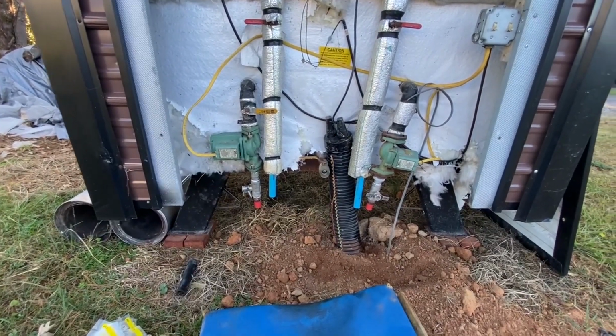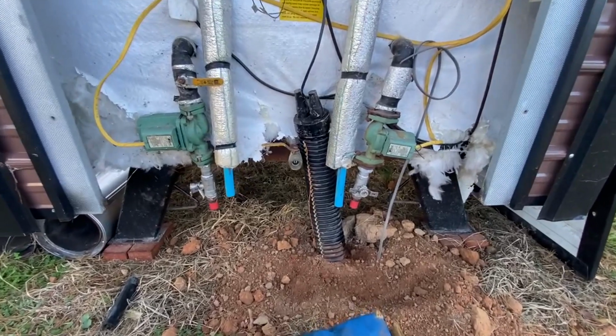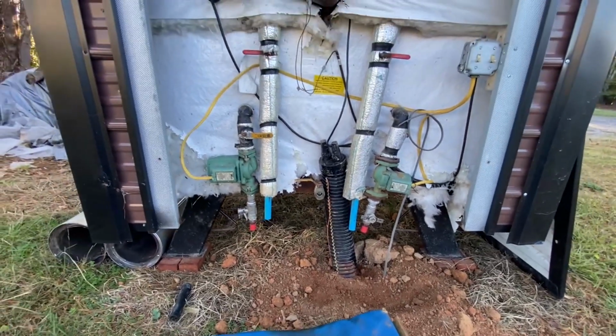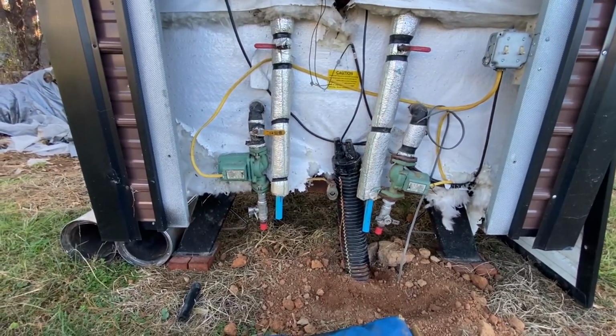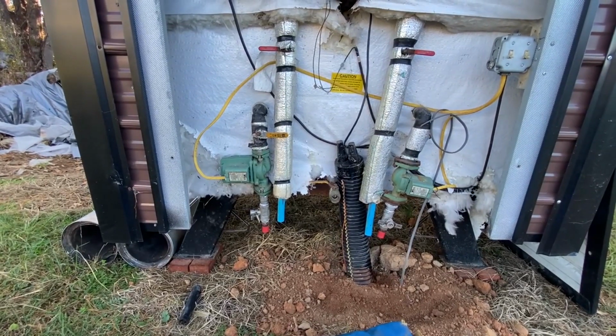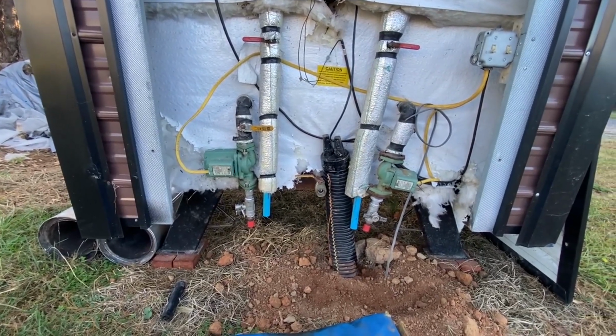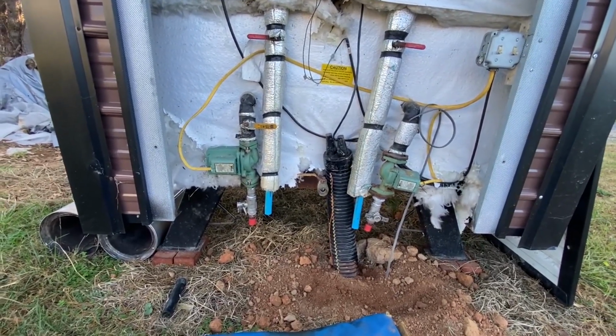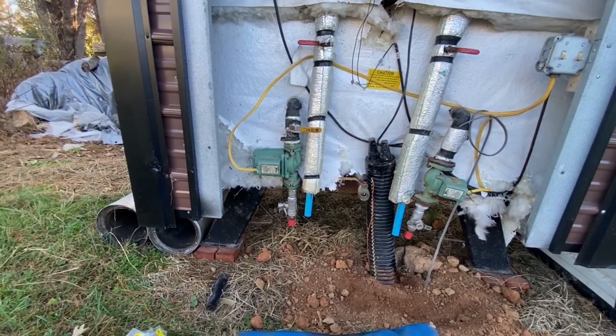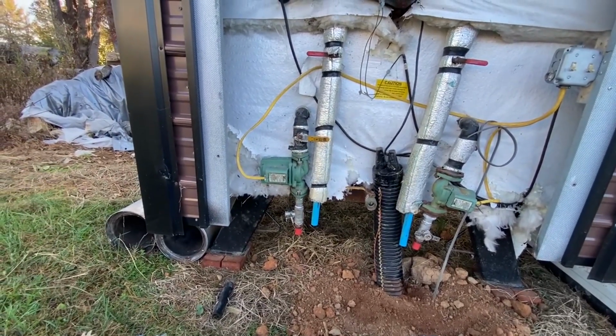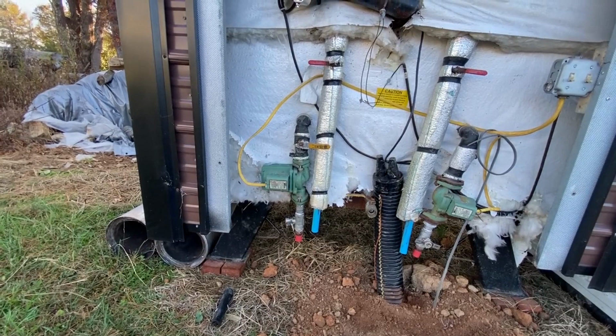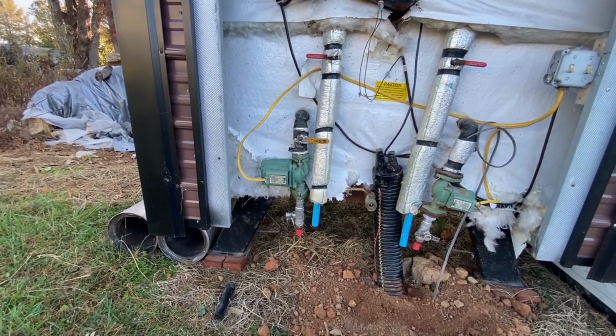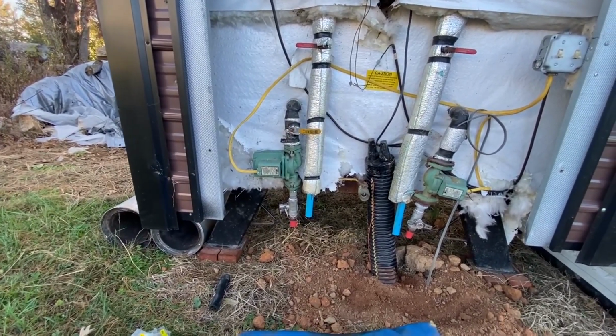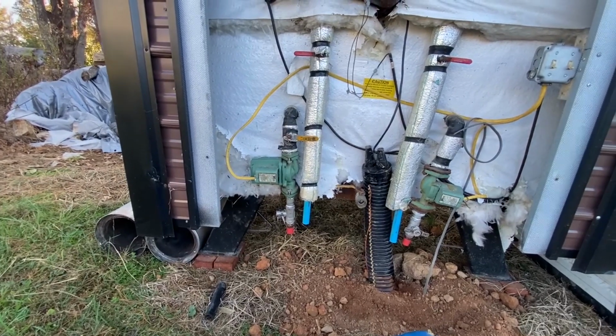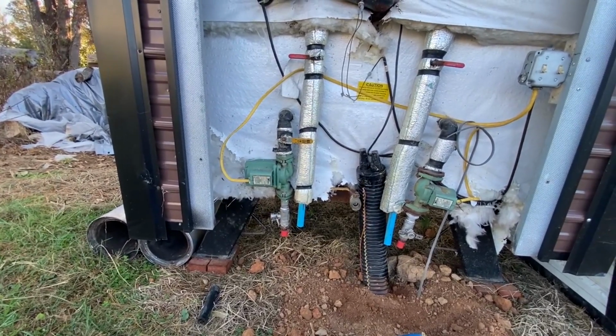On the right hand side we have a loop which was and will be for our workshop, for underfloor heating. On the left hand side is a larger pump, which I'm guessing was circulation for the house, because that was a longer run. That's what I would do too, put in the larger pump for the long run.